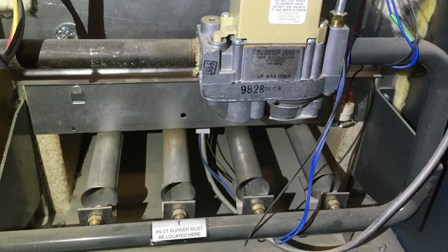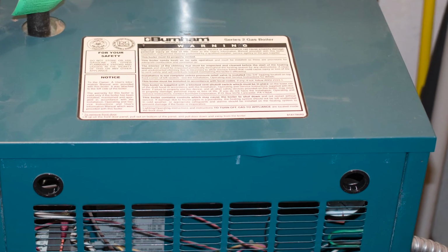So the first thing we'll look at is the burners on your boiler. It's important to have your burners cleaned each and every year, whether it's a boiler or a furnace. The boiler I'm going to show you is a cast iron boiler. I prefer cast iron boilers. They work great. They'll last 30 to 50 years if they're taken care of properly. And back when I was in the HVAC business, I often recommended cast iron boilers. We worked on water heaters, furnaces, boilers, air conditioners, evaporative coolers, and other HVAC equipment. So I have extensive experience in this area.